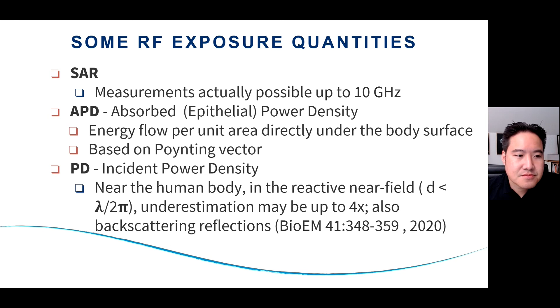So what's the difference between SAR and PD when you're filing something to the FCC? So SAR has the usual liquids and uses a SAM phantom to position devices to head or body structures. But one of the benefits of SAR that for the hand, there's a 10-gram quantity where the FCC limits are at 4 watts per kilogram over 10 grams. But head and body are 1.6 watts per kilogram over 1 gram.